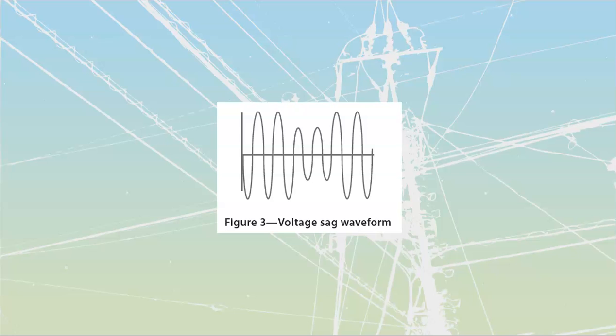Sags, because they are so short, are generally speaking going to be harder to track down. If you have a sag, your customer says, yeah, once or twice a day stuff is happening, ask them to document what's happening in their facility. If there's nothing that corresponds, like a big freezer that's coming on with a massive hermetic pump or things like that, if they can't document something happening inside of their own location that would be causing that sag, then ask them to watch what's going on at neighboring industrial sites. Is the neighboring one always kicking on a massive conveyor or something like that?